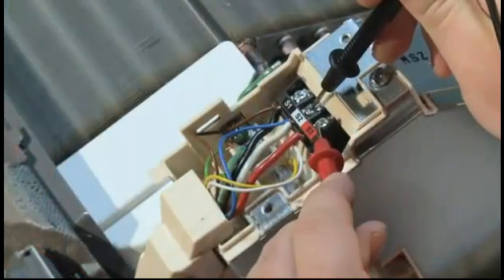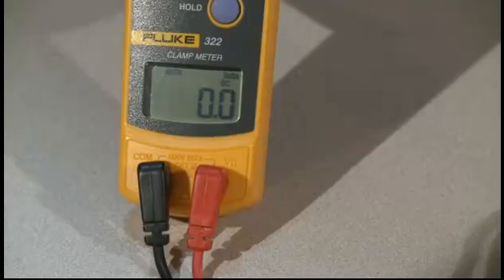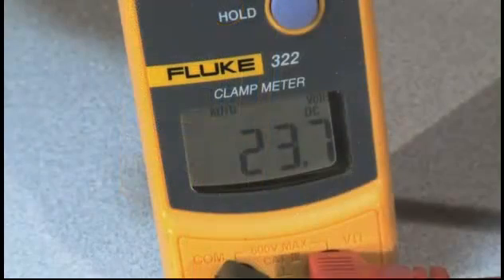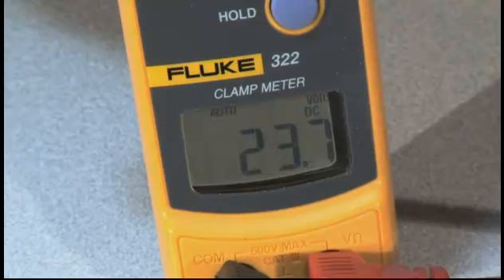Start by checking outside and verifying a steady DC voltage across S2 and S3. Once you've done this, go to your indoor unit and check your DC voltage again at the indoor terminal block S2 and S3. One reading you could get would be 0 volts DC at the indoor unit, but 24 volts DC outside. In this case, start by looking around for what could be breaking your communicating voltage.